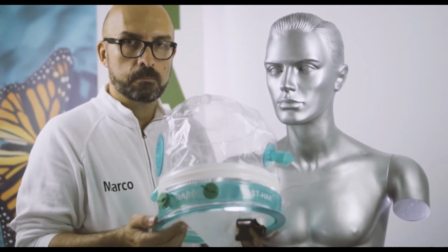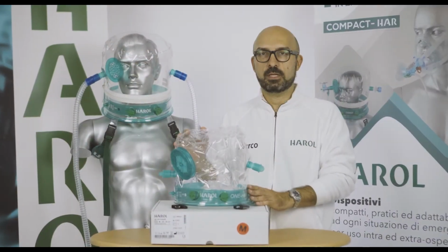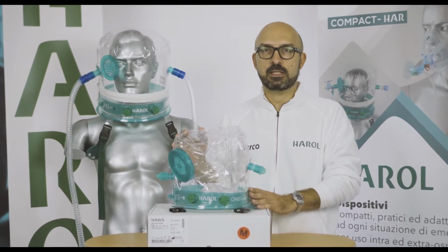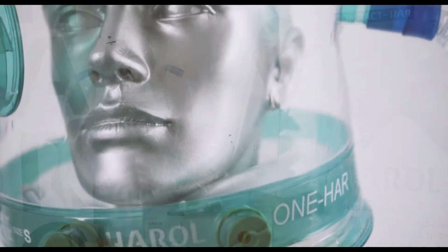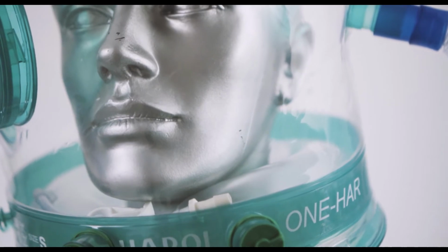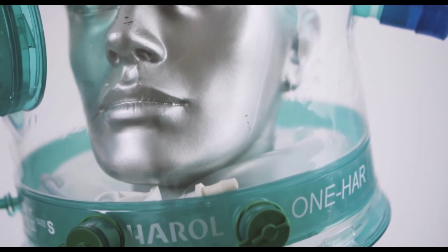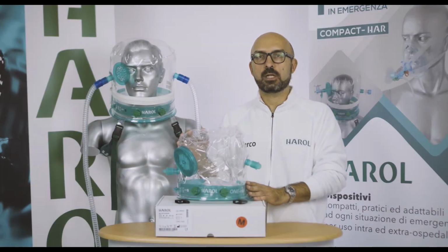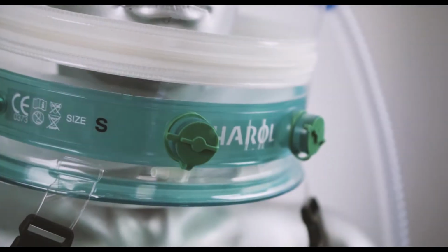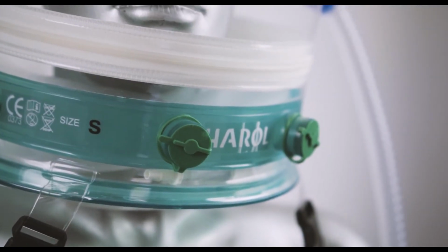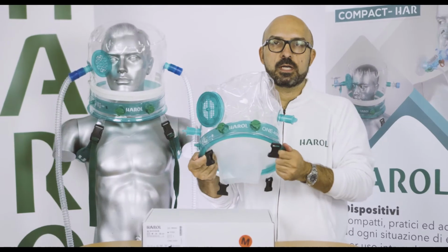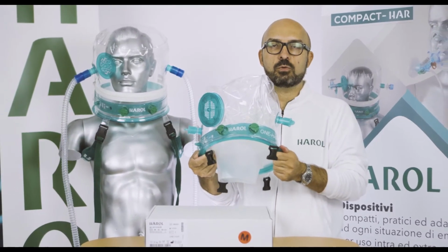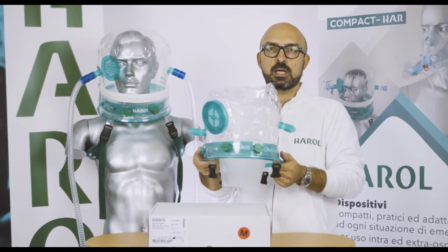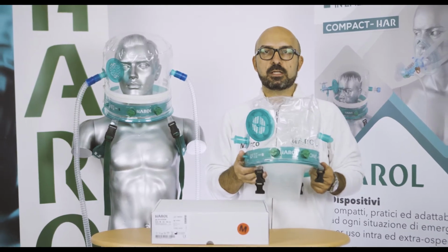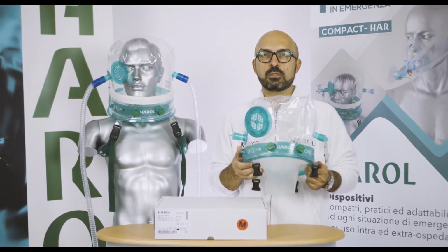The helmets are made in PVC and are both latex-free and DEHP-free. It is for a single patient use and non-sterile. The volume of the tent is around 11 liters, a small volume to enhance the synchronism with the ventilator. The helmet is equipped with a rigid ring to maintain the shape during the therapy. Weight is approximately 320 grams or 400 grams based on the model.